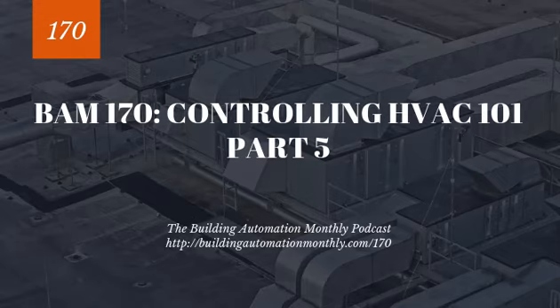There's multiple different things that can happen, but primarily when you hear low DeltaT syndrome, and you go and measure your pre and post coil temperatures, you look at the temperature gauges on the piping. This is another reason why on large air handlers, I recommend things like the Belimo energy valve, where you actually have temperature sensors and flow sensors, and you can really get a good idea on coil performance, especially for critical airside systems. But regardless, you measure your GPM, you measure your temperature, and if you see that, hey, I've got 48 coming in and 50 going out, then that's an issue, right?